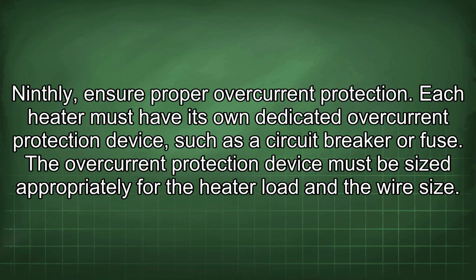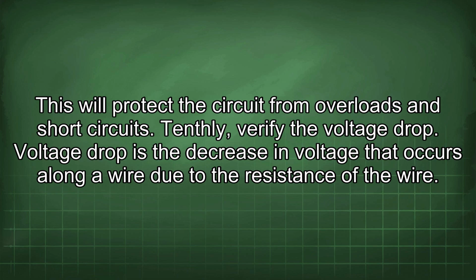Ninthly, ensure proper overcurrent protection. Each heater must have its own dedicated overcurrent protection device, such as a circuit breaker or fuse. The overcurrent protection device must be sized appropriately for the heater load and the wire size. This will protect the circuit from overloads and short circuits.